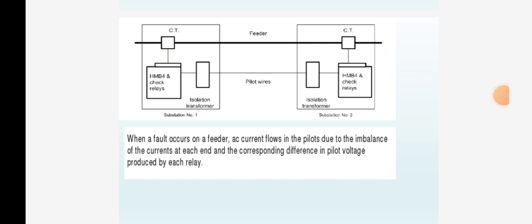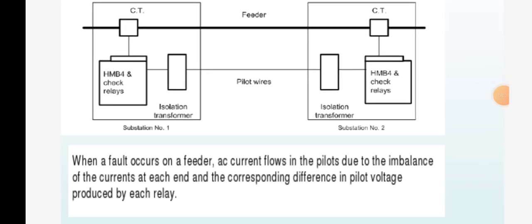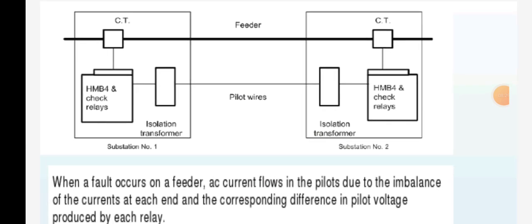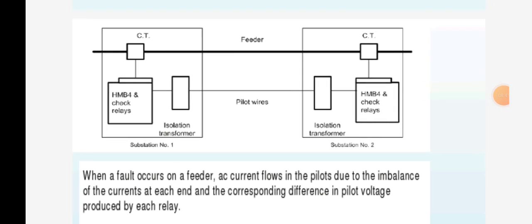In this diagram, we can observe the two current transformers and feeders. The pilot wire is connected to both current transformers. It has the HMB4 check relays, isolation transformers, substation number 1 and substation 2, connected in between two substations. When a fault occurs on a feeder, the AC current flows in the pilot due to the imbalance of the currents at each end and the corresponding difference in pilot voltage produced by each relay.